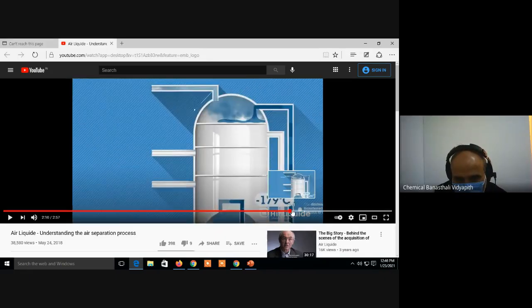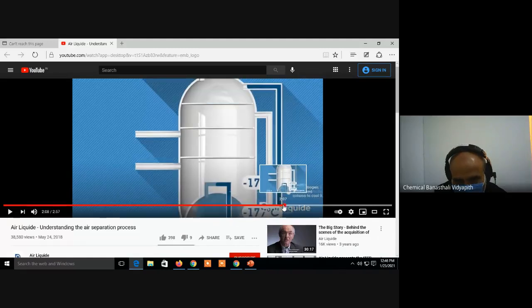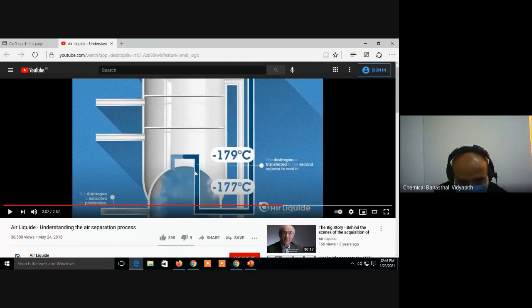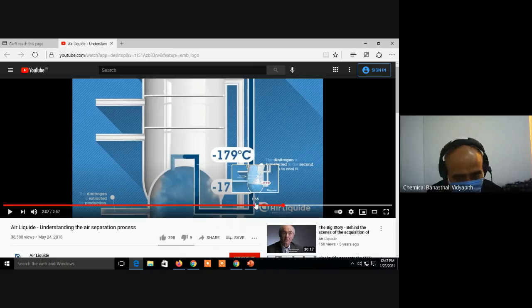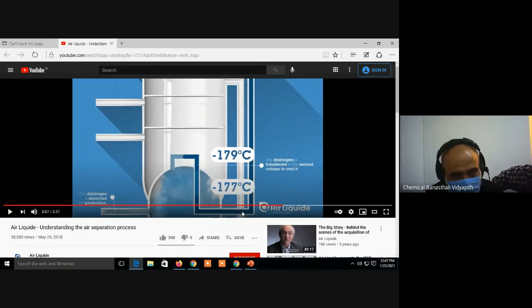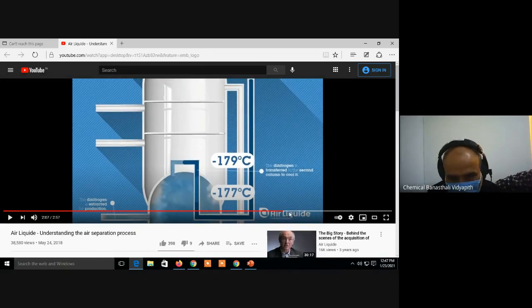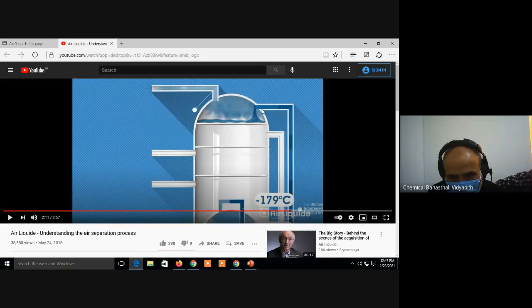Now further, just a moment. You see in this channel, you can see the color of the nitrogen is changing. What is it trying to represent? They are trying to say that it is being liquefied and the temperature is dropping. How is the temperature dropping? Because of this heat exchanger, and also another device which uses the Joule-Thomson effect. We are cooling the nitrogen. In the second column, what do we need? We need low temperature nitrogen. You can see from the top, it is cold nitrogen which is entering. Some part of it then vaporizes and moves out from the top. So why do we put this cold liquid nitrogen from the top?